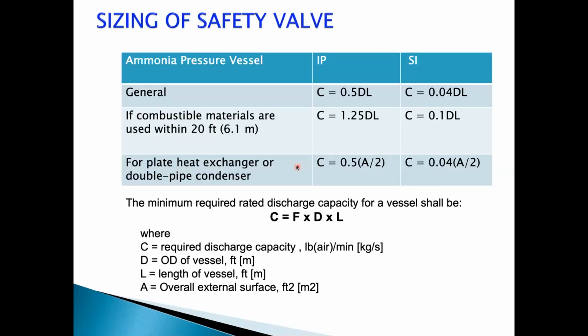How do you calculate the safety valve capacity? This is the formula given by the ASHRAE standard 15 and IIAR standard 1 to calculate your capacity. C is the capacity required for your safety valve. F is the correction factor. For ammonia, it is 0.5. And F, when you are in IP, it is 0.5, and in SI, 0.04. D is the diameter of the vessel, and L is the length of the vessel. You can calculate this.